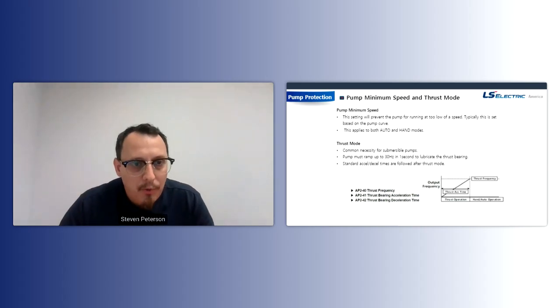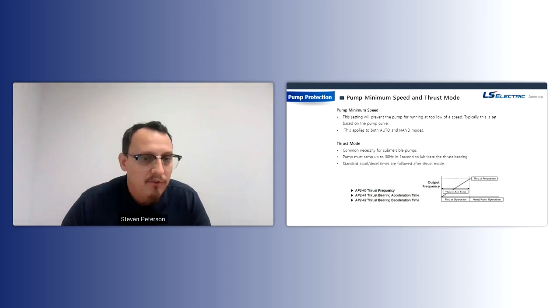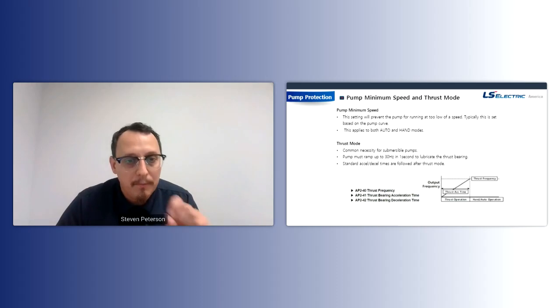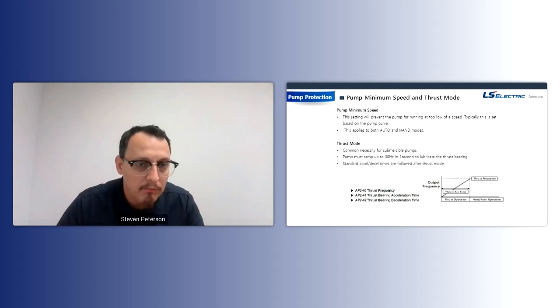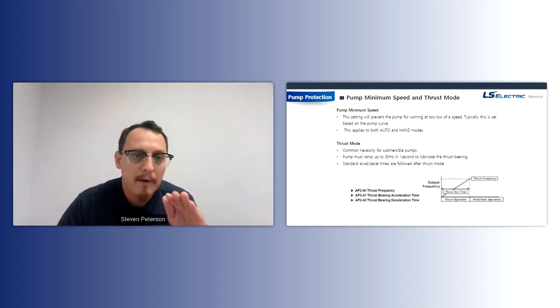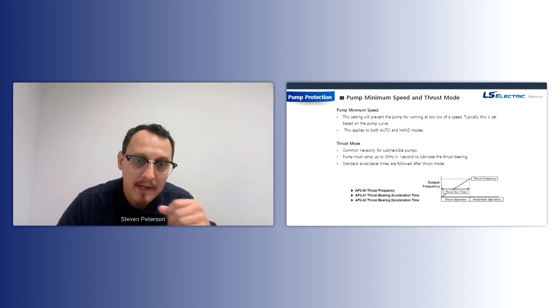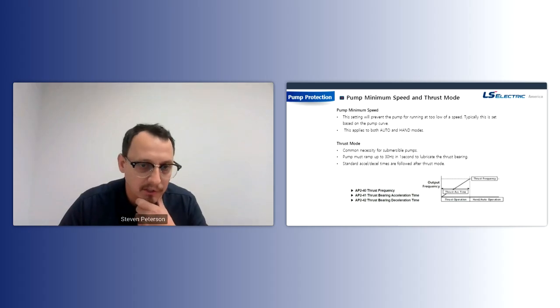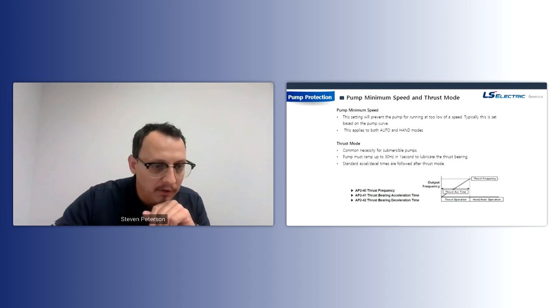Also related to that, we have a thrust mode. For those of you that do submersible pumps, it's a very simple thing. All you do is program in your thrust frequency, which will be like 30 hertz, and it's going to ramp up from 0 to 30 hertz in 1 second. That's fast enough to lubricate that thrust bearing. And then after that, it's going to follow your standard accel and decel time. This is great for submersible pumps.